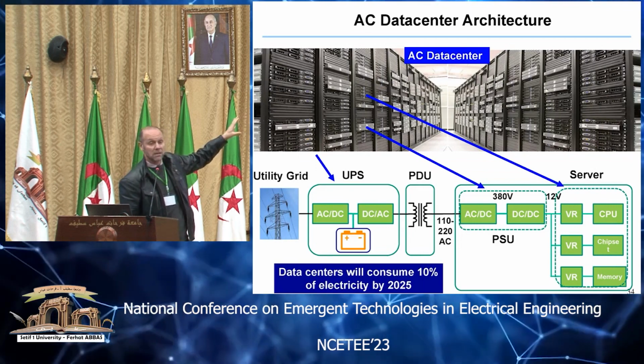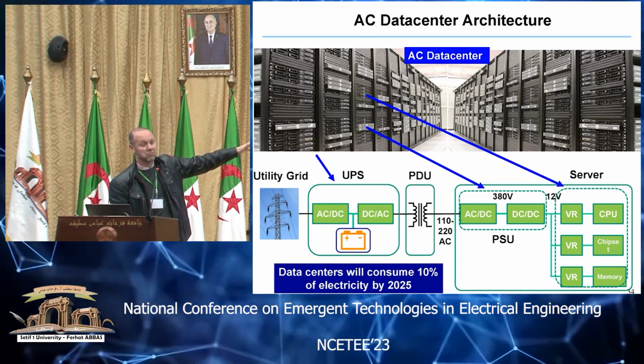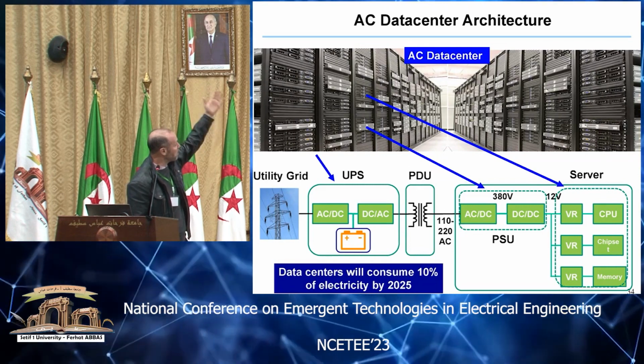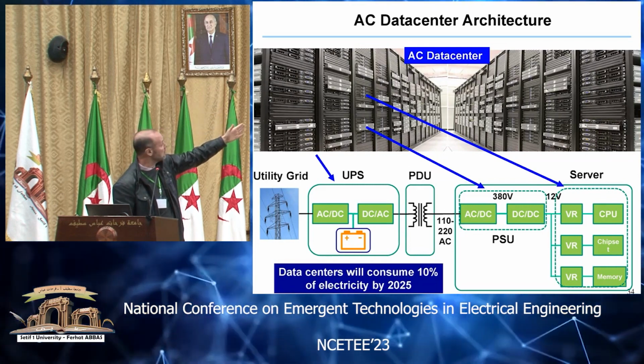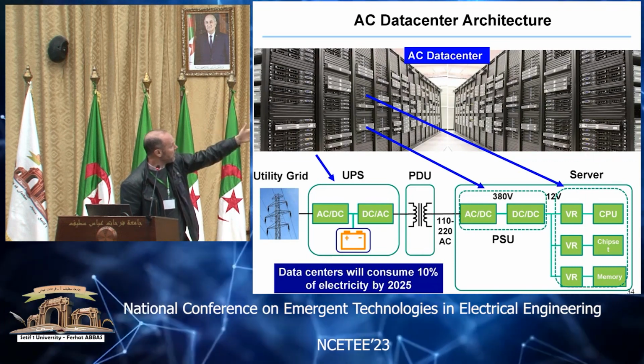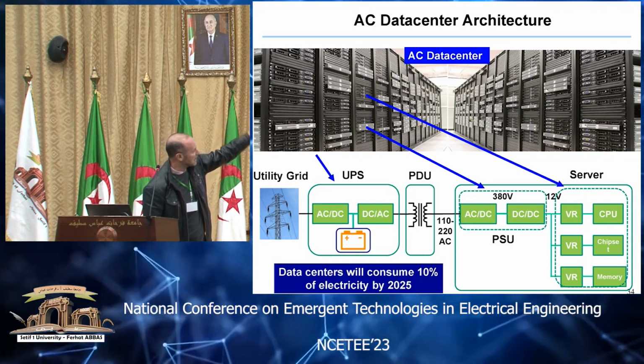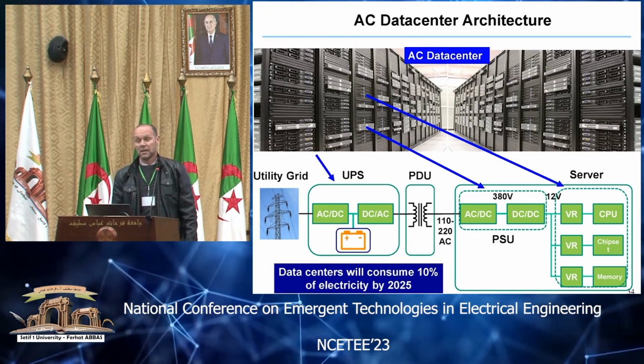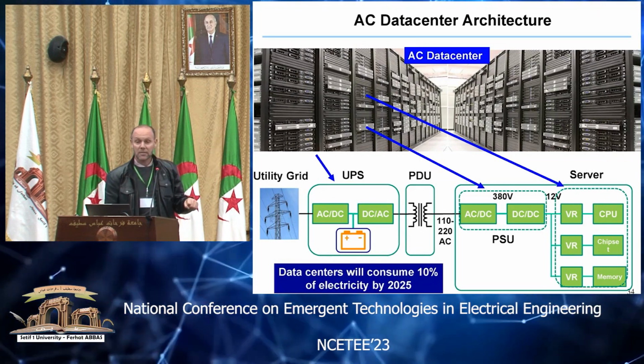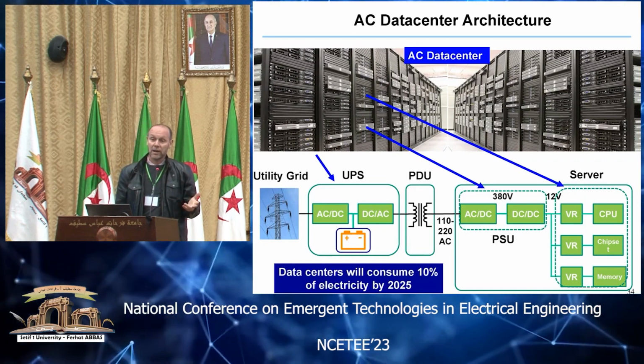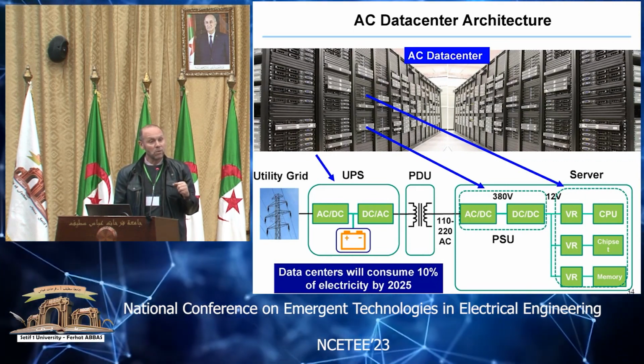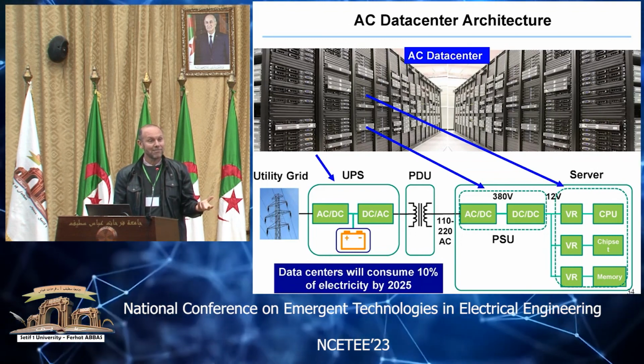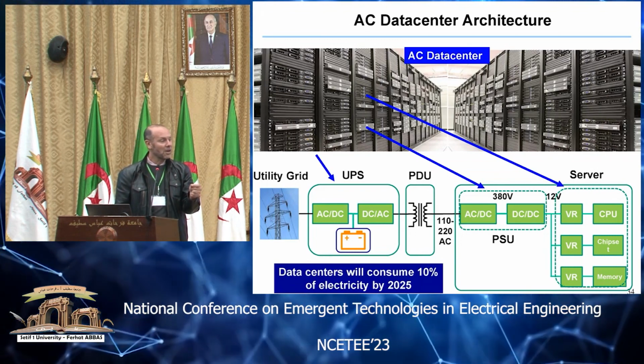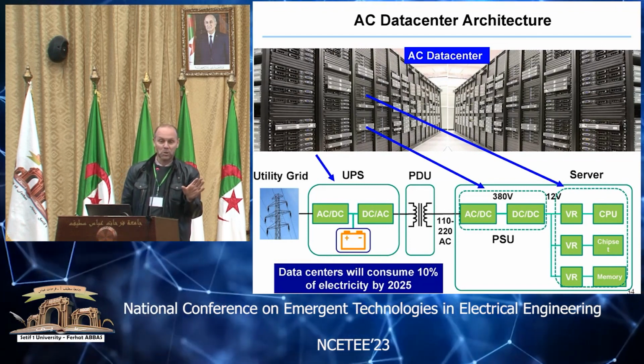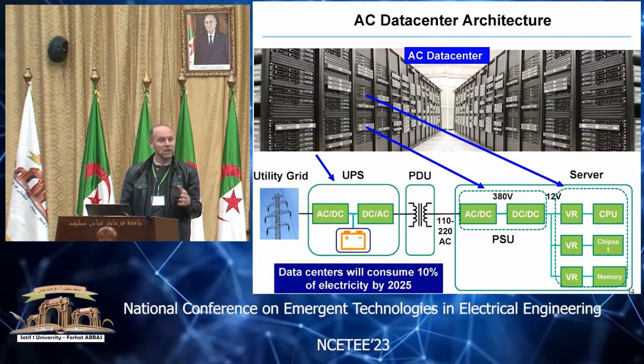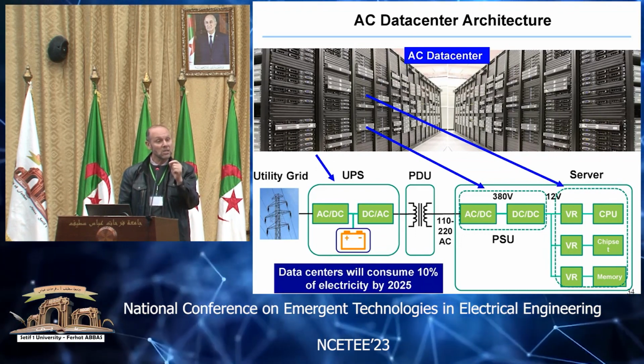This is the architecture of existing data centers. We have the grid, then UPS systems, which convert AC to DC, DC to AC, then storage, then the servers where voltage regulators supply the required voltage. Can you see these green boxes? These are conversion stages. Every time we do conversions, we have losses. There is no 100% efficient conversion system - so far it does not exist. You can achieve maybe 99%, but there are always losses.